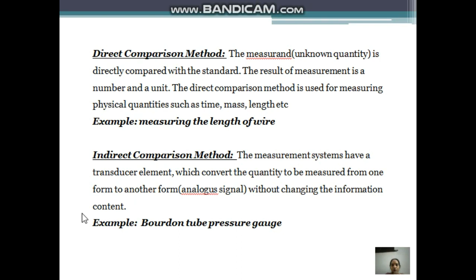In the Bourdon tube pressure gauge, the input parameter is pressure. By letting pressure into the Bourdon tube, it expands, and a pointer attached to the tube moves along the calibrated pressure scale, from which we get the pressure reading. So we are not getting the measurement directly; the tube expands and the pointer moves along a calibrated scale, so we indirectly get the pressure measurement. This is called the indirect comparison method.